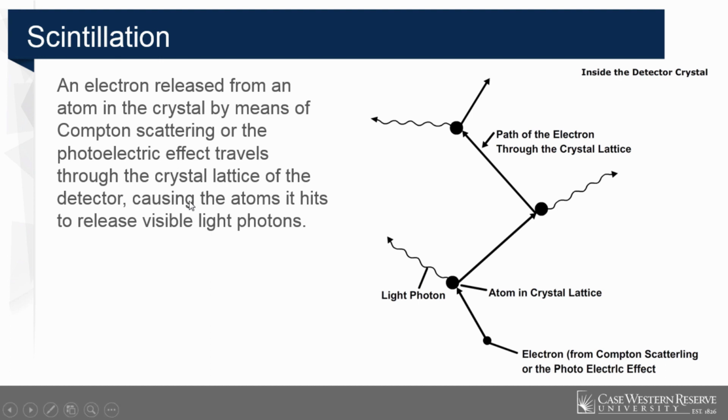So what's happening is a process called scintillation. Through Compton scattering or the photoelectric effect, you have those electrons, and they will interact with the nearby atoms in this tightly packed, dense material called crystal. So the atom will vibrate, release energy in the form of visible light photons, and after a few iterations, the incoming gamma photon will be gone and turn into those light photons.